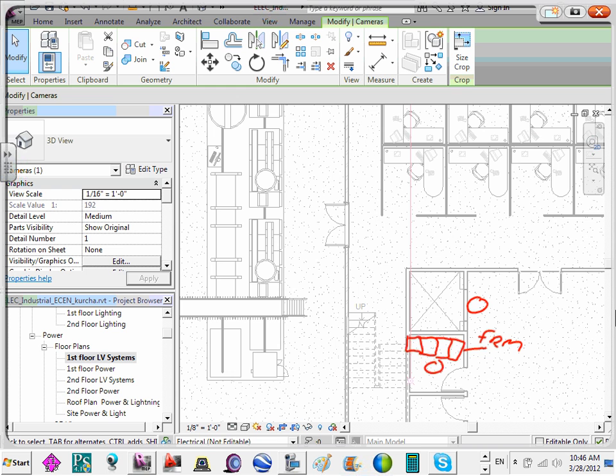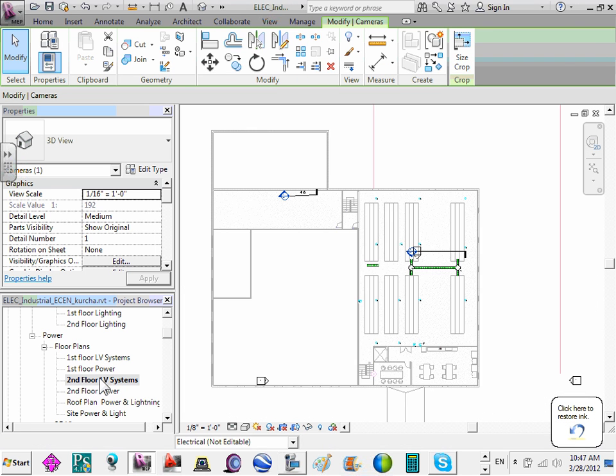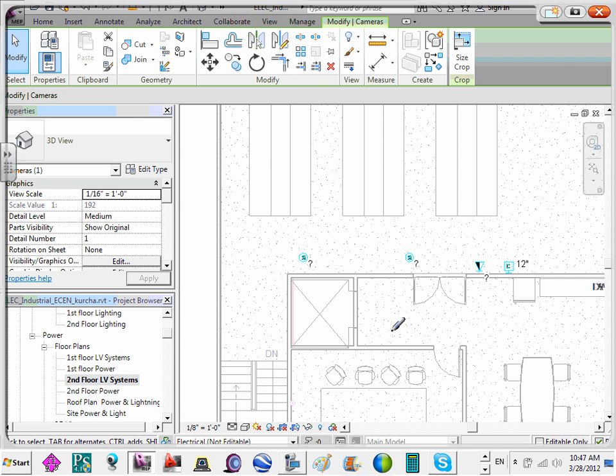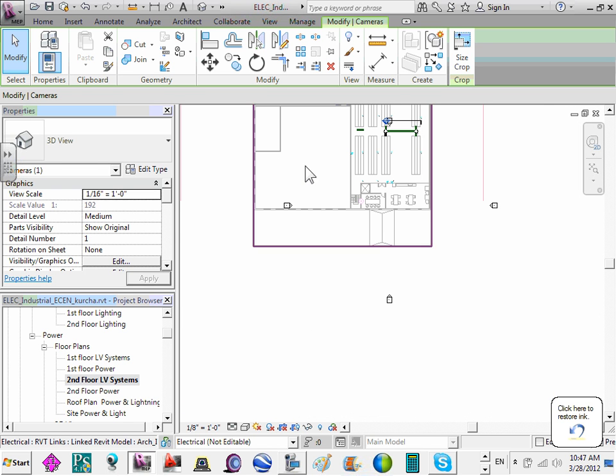And the firefighter helmet, there's a light on. All it does is activate a light saying this cab is about to be shut down, unless the firefighters come in with their key and then they can control it. So you're going to have that on the first floor. On the second floor, you're going to have another one. And these are all going back. And there's going to be another S fire smoke detector. Back onto the first floor here.